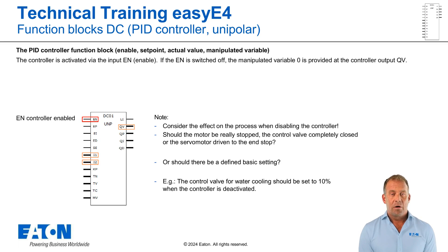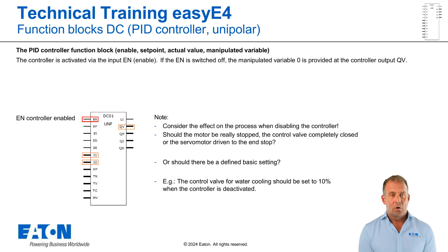The controller can be deactivated by the program via the input EN (enable). At the output QV, the manipulated variable is set to zero. But be careful — consider the impact this will have on the process. Should the motor be stopped, the control valve completely closed, the servo motor driven to the end stop, or should there be a defined basic setting? For example, the control valve for water cooling should be set to 10% when the controller is deactivated.